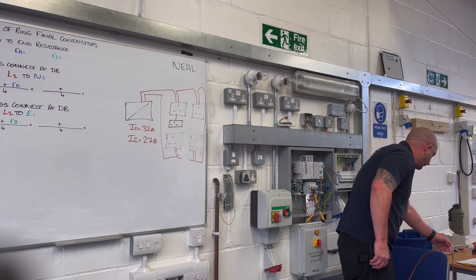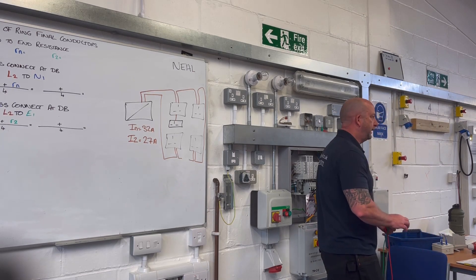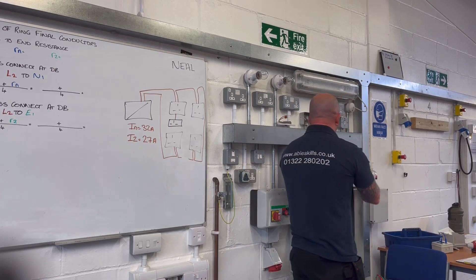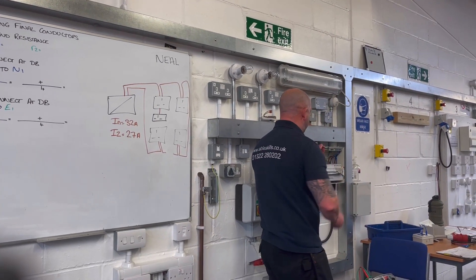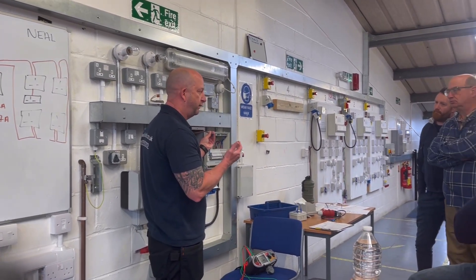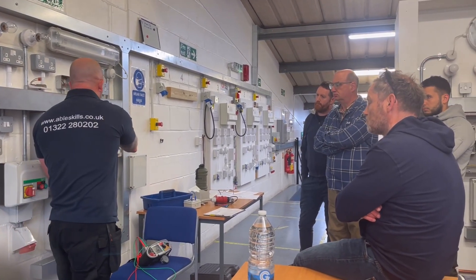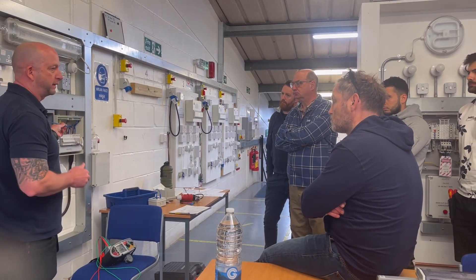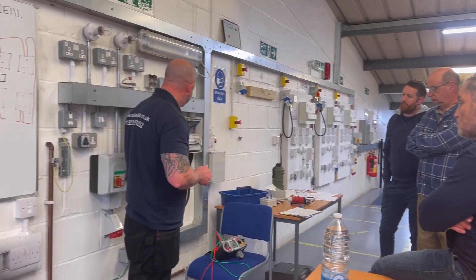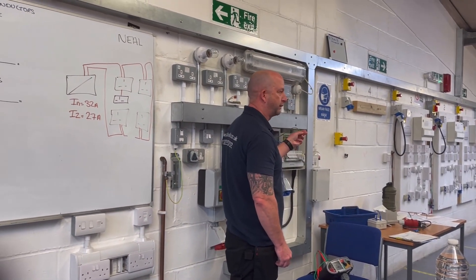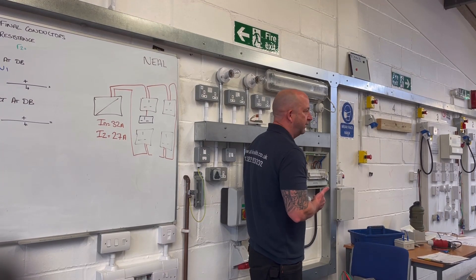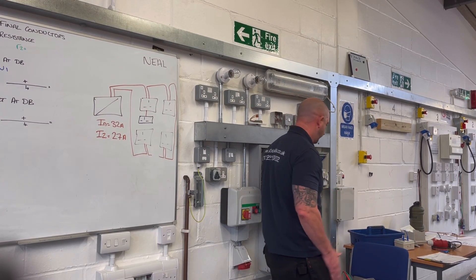So there are three steps to continuity of ring final. Step one is end to end — we're going to measure our loops of cable. We're going to measure the line (brown) loop and record that as little R1. We'll do the same with the neutral loop and record it as little Rn, and the same with the CPCs as little R2. We're just making sure we've got a closed loop of cable, because if we haven't, then no way is this a ring final circuit.